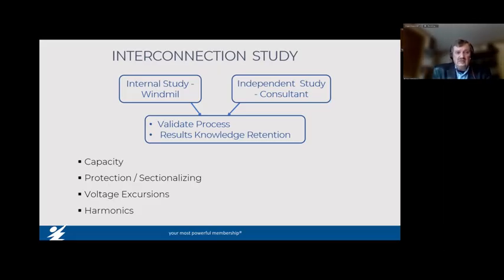So anyway, we studied to make sure we had sufficient capacity in all the wires and equipment. We studied to make sure that if there was an outage, this thing would shut down and not feed out into the distribution grid, and that it would be able to handle any outages from the system or would not cause any issues. We tested the voltages, studied the voltages, and we studied to make sure we weren't putting any bad harmonics out onto the system that would cause any neighboring members or customers any issues, and that turned out real good. So that's how we did the study. The first time for us, it was challenging. It was a lot of fun, and we ended up with a very good result.